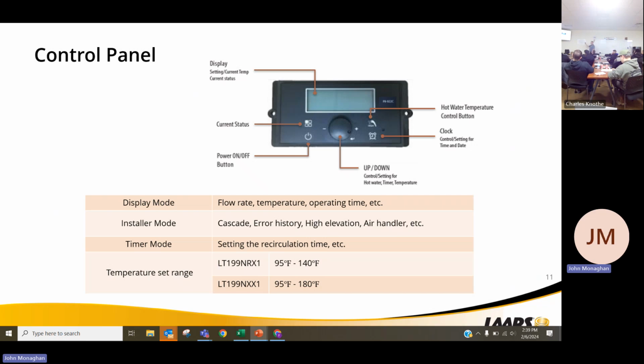The faster that water is spinning, the higher the flow we're going to be registering on the display. We can also go through and set our recirc time, what we're doing for our recirc, and our temperature range. We can also change it from residential to commercial if we need to elevate above the 140 degree mark. One thing I can say, if we are going to elevate our water temperatures over 140 degrees, it's going to ask you for your vent material. And if you select PVC, it's not going to let you go higher than 140 degrees. You have to tell it you're using something other than PVC in order to get it to 180.